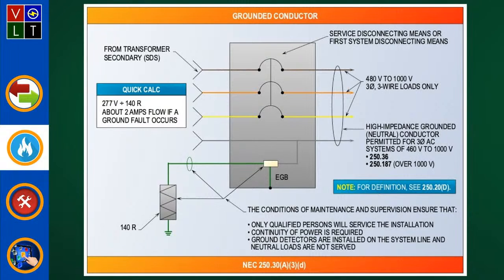Let's say I have my panel board, run a circuit to a box, then come over to a step down transformer going to a 120/208-volt system, and then out of that panel board into that same junction box where the 480/277 circuit is. You've got 277 volts, so you need to identify the difference of those neutrals. If you've got a gray, that's for the 277, and the white's for the 120/208. So it's not only apparent when you have two different sources coming into a building, but also if you step it down within the same building.